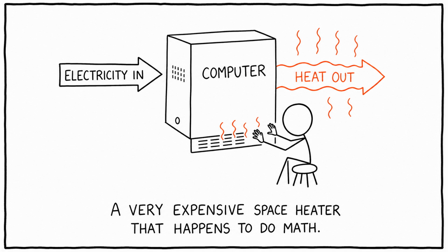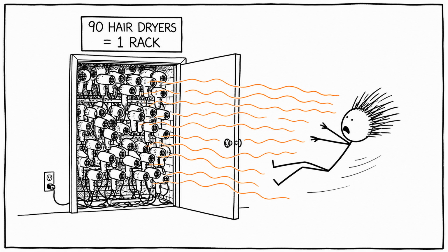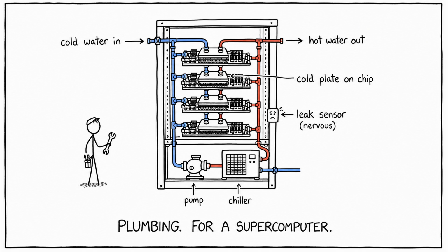Third, heat. Every watt that goes into a chip comes straight back out as heat, all of it. A data center is, thermodynamically, a very expensive space heater that happens to do math. A 130 kilowatt rack is like standing 90 hair dryers in a closet and switching them all on at once. Plain air cannot carry that much heat away anymore, so AI racks move to liquid cooling. Cold water piped directly onto the chips, pumps, chillers, heat exchangers, and leak sensors everywhere. It is plumbing, but for a supercomputer.